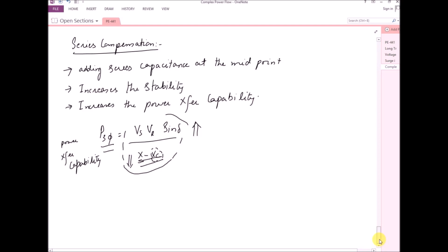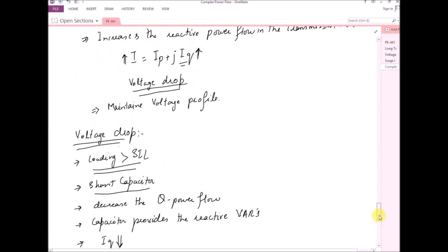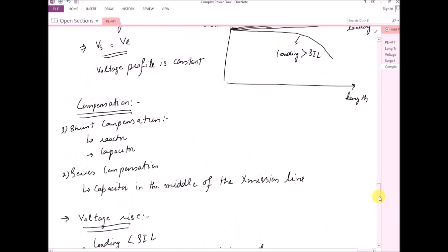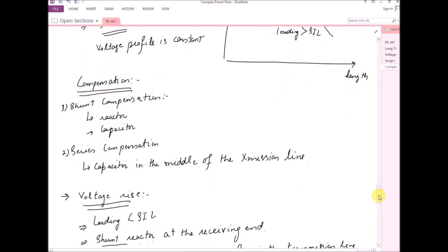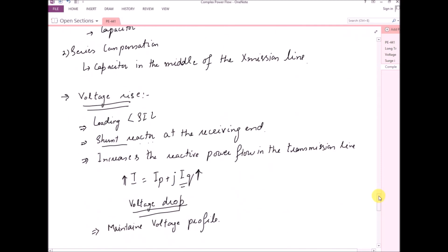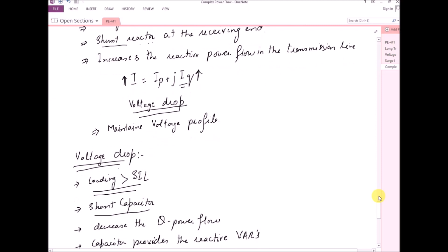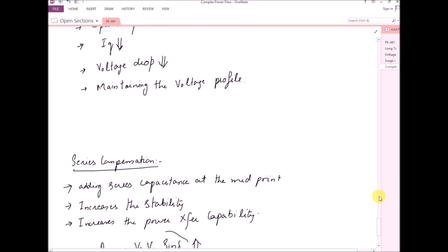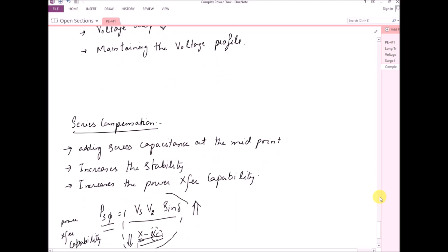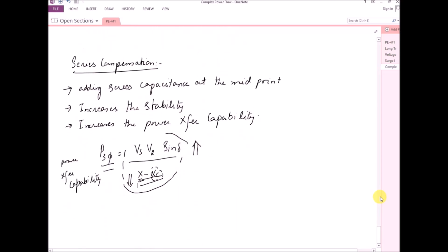These are the three types of compensation used in transmission lines. First, shunt compensation with a reactor at the receiving end for a voltage rise problem. Second, a shunt capacitor at the end of the line for a voltage drop problem. Third, a series capacitor at the middle of the transmission line to increase the power transfer capability of the line.